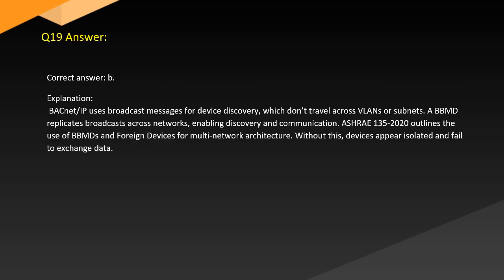Answer. Correct answer: B. Explanation. BACnet uses broadcast messages for device discovery, which don't travel across VLANs or subnets. BBMD replicates broadcasts across networks, enabling discovery and communication. ASHRAE 135-2020 outlines the use of BBMDs and foreign devices for multi-network architecture. Without this, devices appear isolated and fail to exchange data.